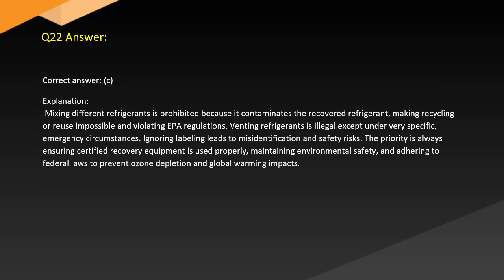Answer. Correct answer: C. Explanation. Mixing different refrigerants is prohibited because it contaminates the recovered refrigerant, making recycling or reuse impossible and violating regulations. Venting refrigerants is illegal except under very specific emergency circumstances. Ignoring labeling leads to misidentification and safety risks. The priority is always ensuring certified recovery equipment is used properly, maintaining environmental safety, and adhering to federal laws to prevent ozone depletion and global warming impacts.